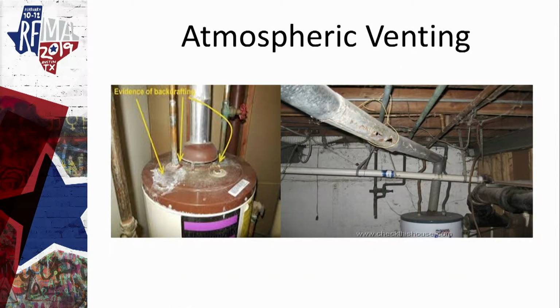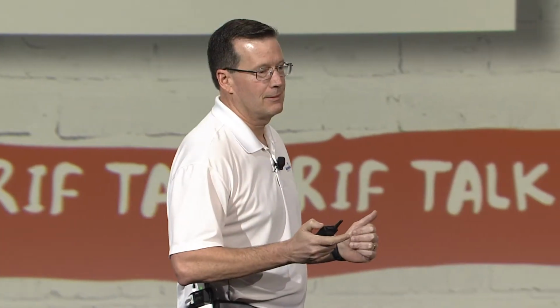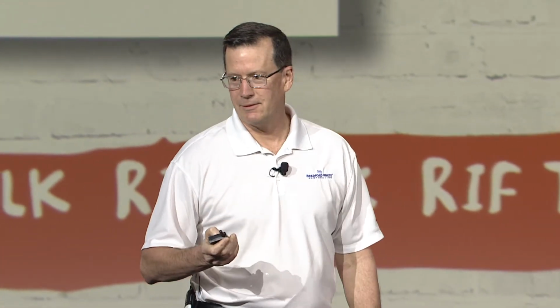Venting: if you see white residue on the top of your tank, you have a potential problem. Address it, because the other picture is when the products of combustion get into the vent pipe and it's not getting out of the room properly, it condenses. Condensate is acidic, and as you can see in this picture, it's putting a hole in it. And what does carbon monoxide do to human beings? Right, it's not good for us.